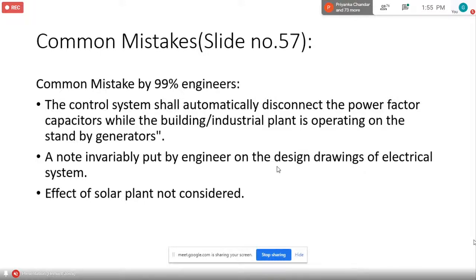If only the switch supply is there, if the generator is stepping up the supply and then going through the same breaker, then only it will be sensed. Okay, so in most of the cases, when the generator supply comes in, the power factor system is automatically disconnected. You don't have to do anything, and you can run the power factor correction capacitors on generator. There is not a problem because the load is always there, and the capacitor load and power factor together is a good power factor. The thing is that these people learn somewhere that the generators cannot work on the leading power factor. Yes, it is true, but they are not going to see that power factor at all.